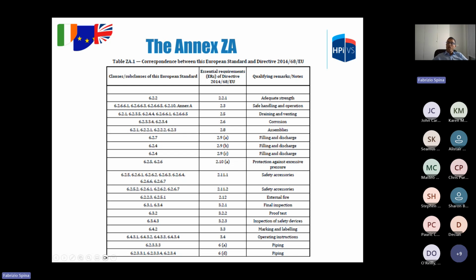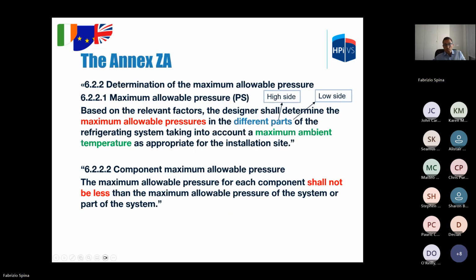Now we can start reviewing the main points of EN 378 Part 2, as outlined in the Annex ZA. We will evaluate all these points, the main points listed in this annex. 6.2.2 Determination of the maximum allowable pressure. The maximum allowable pressure, PS, must be defined in the different parts of the refrigeration system, typically the high side and the low side, taking into account the maximum ambient temperature and relevant factors. Relevant factors are maximum ambient temperature, method of defrosting, for example, solar radiation, fouling. All these factors must be considered when defining the maximum allowable pressure of the system.